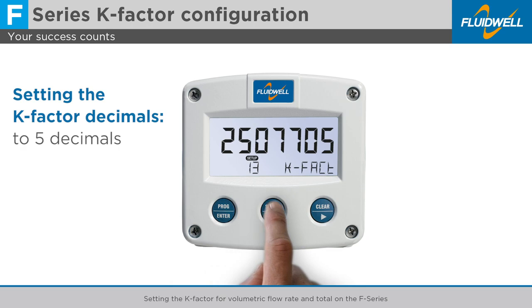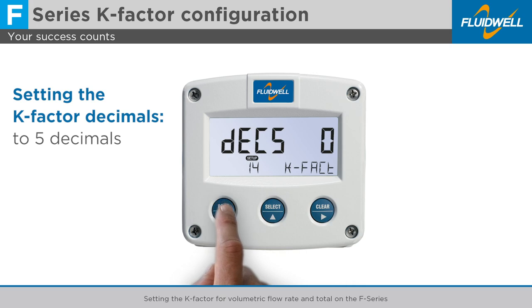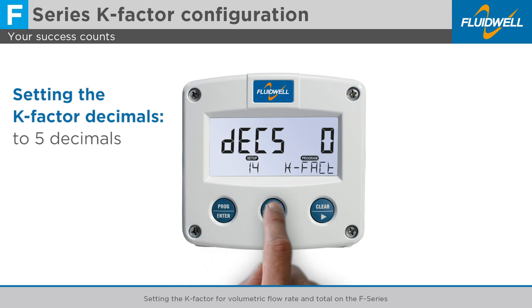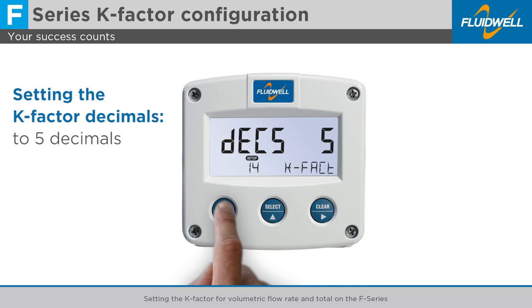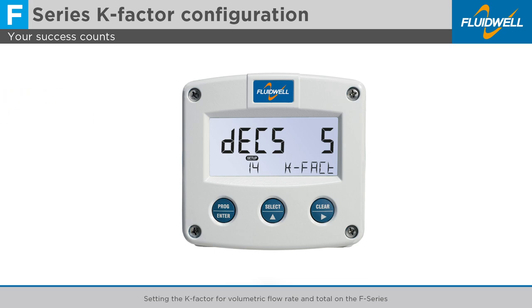Press Select to go to Menu 14, K factor decimals. Press Prog to set the K factor to 5 decimals. Press Prog to store the K factor decimals. The K factor and engineering unit for the total are now correctly configured. Next, we are going to set the K factor and engineering unit for volumetric flow rate measurement.